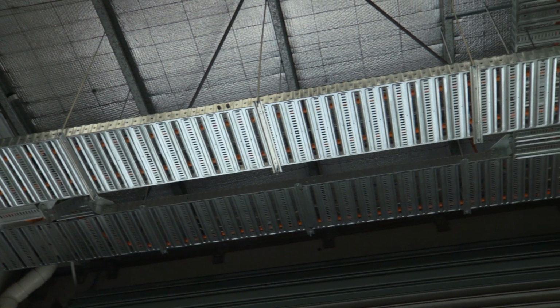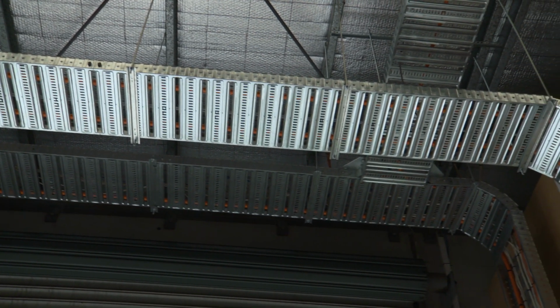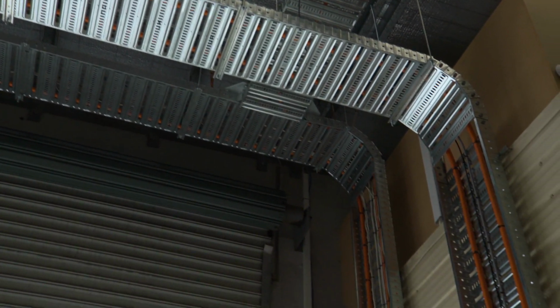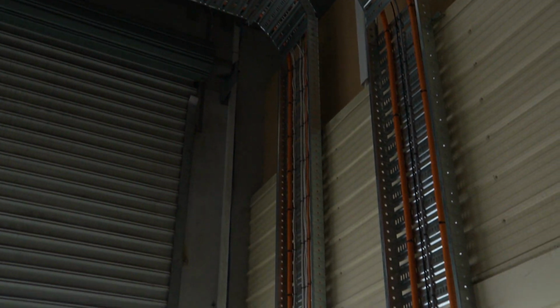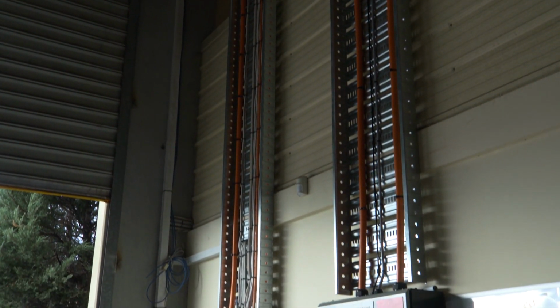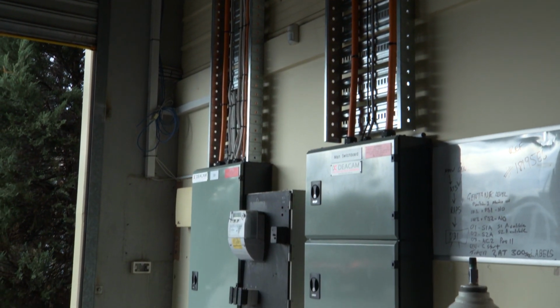The finding was that we were basically at peak load, which means that we've got a capacity of 100 amps into the site, which realistically means they give us about 80. And at times we were hitting 123. So unfortunately we were above what we were being supplied by the grid. The wiring going down from our mains all the way down to our subboards were probably not as set up the way they needed to be.